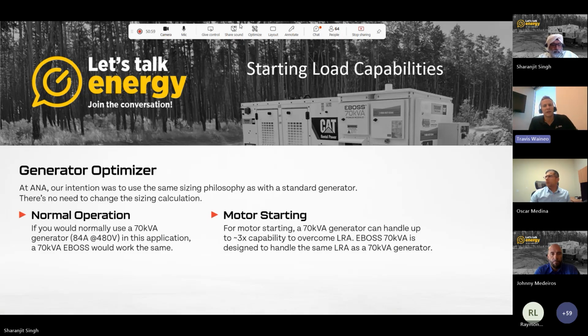The other thing we didn't want to do is we didn't want customers to have to really think through or change the mindset for how they sized a system when it comes to the hybrid system. So if they said, okay, I know I could start a certain piece of equipment with a standard 70 kVA generator, the intention was that when you have a hybrid system, you can start that same piece of equipment with a similar rating. So if you can start something with a 70 kVA gen, we designed it so you could start that same gear with the 70 kVA hybrid system here.